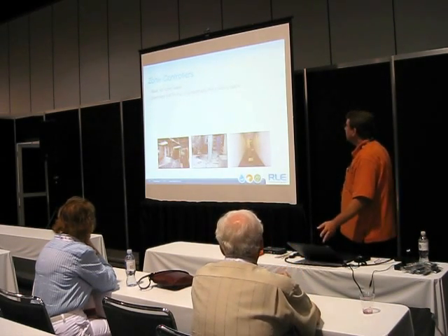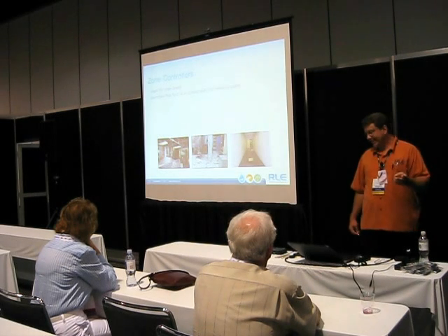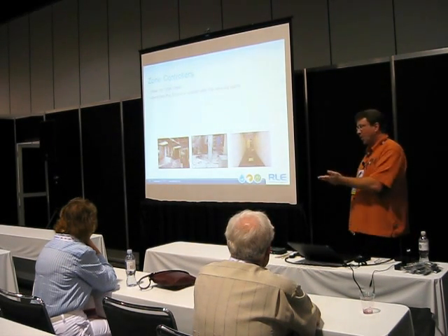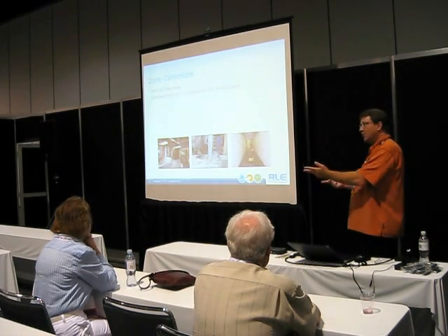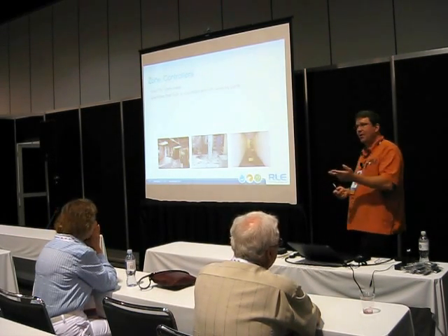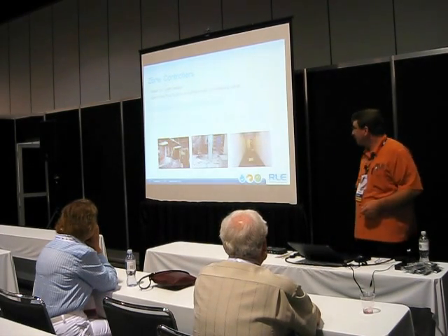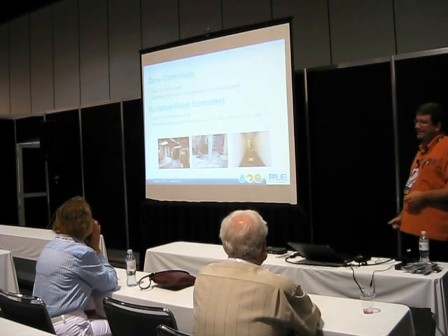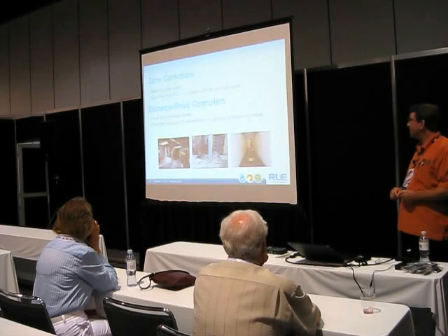And then when you're looking at the controllers, there are really two types of controllers we can integrate leak detection cable into. We can do a zone system, which will tell you water's in contact with the cable. It won't tell you where. So maybe in a small area where you can walk in and see a cable on the floor, you can identify where that issue is easily. A zone controller works well. The distance read controllers available on the market will pinpoint the exact location. And I'll give you a quick example of that as I wrap up here in a couple minutes.